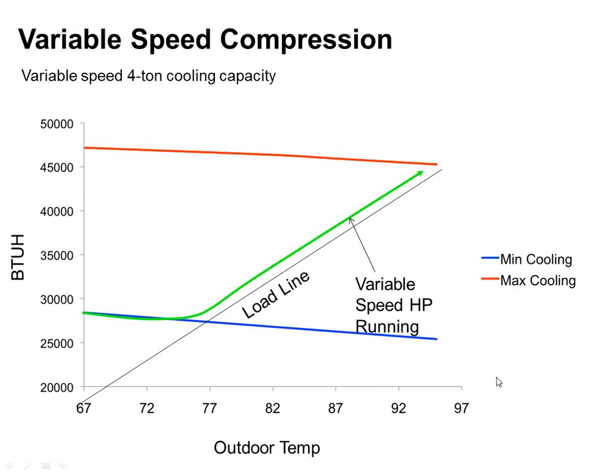And then I have to have a reasonably efficient compressor. You'll find variable speed rotaries and variable speed scrolls on the market, both for different reasons. They have different advantages, if you will. The real advantage of a variable speed scroll is that, compared to a rotary, I can overspeed it more. I can safely run it at a higher RPM if I want to. Sam, I see your question about the inverter, and we're going to answer that in a second. I can run it at a higher RPM, and hence I can get more capacity out of it on a cold day, right? So I get better heating performance out of variable speed scrolls.